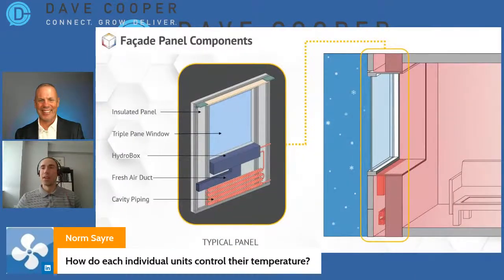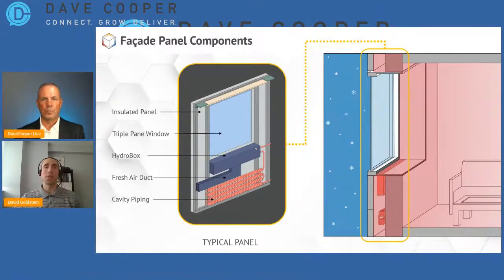Norm Sayre: how do each individual units control their temperature? Hey, that is by far an amazing question. Okay, well let's bring the slide deck back up. There you go. This is a really important aspect - if we're going to talk about thermal comfort, people need individual control. Basically what you see here, I mentioned this is a fan coil unit that sits under the window, which is basically a fan and a coil, a typical fan coil unit, although there are some differences which we probably don't have time to get into right now. But basically within this enclosure is a control valve. This fan coil unit and the radiator piping are all in series, so we basically have one control valve that sits inside the unit, and that's going to control your total output to the apartment because it's controlling the radiator and the fan coil unit. So every room will basically get individual control because they'll be able to open and close that control valve.